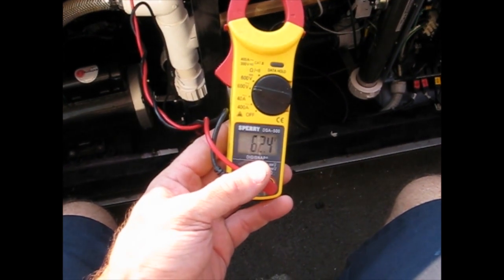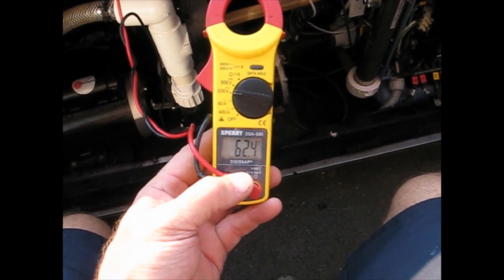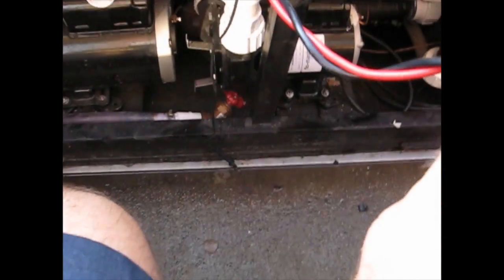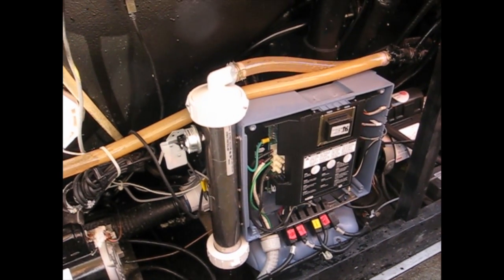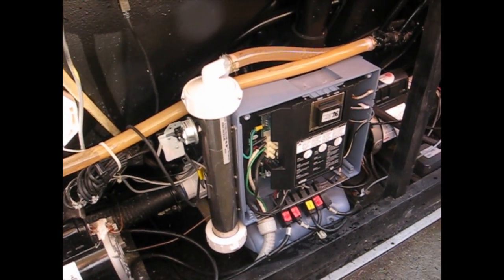I felt a shock a minute ago and you can see it's showing 62.4 volts in the water. I've got my ground to the water on the concrete, my other lead in there. So I wonder what's wrong with this. I'm going to open this GFI breaker up and see, but I would say we've got a ground not hooked up. Let's see if we can find it.